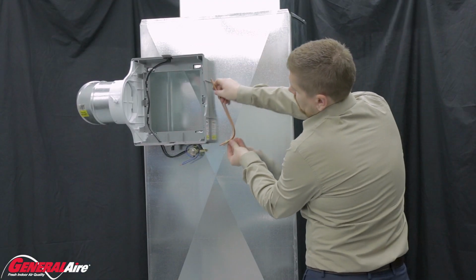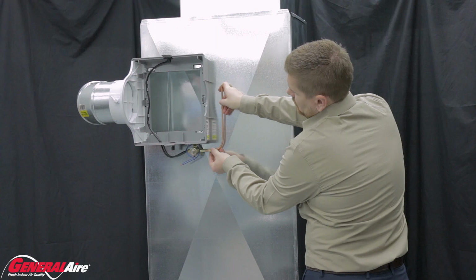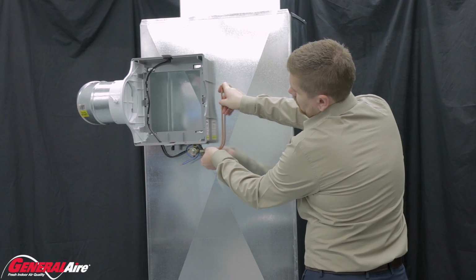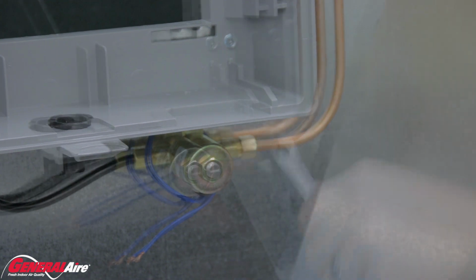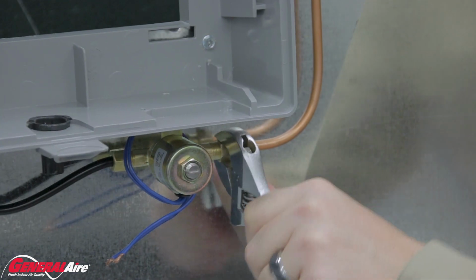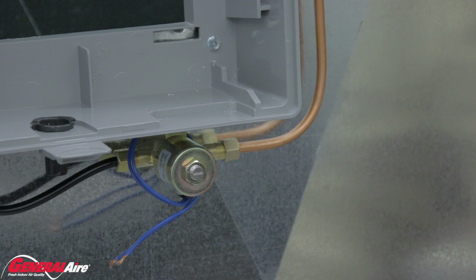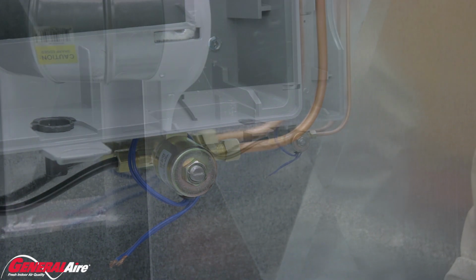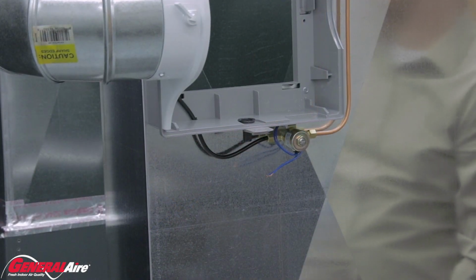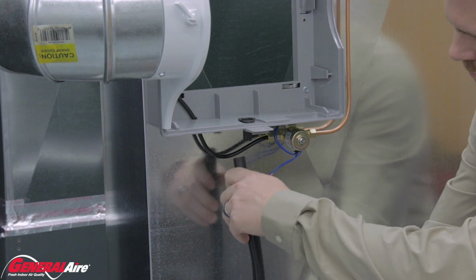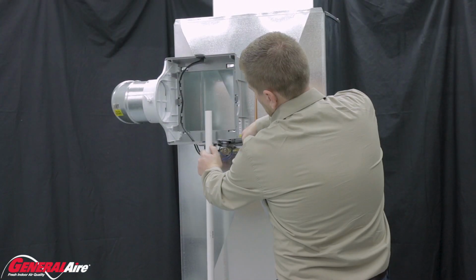Your water line runs down the side of the humidifier to the inlet of the solenoid. Take off the compression fittings and install the pipe, tightening the fittings back on with the crescent wrench using the same method as the saddle valve. The water supply is now set up. If using 5/8 tubing, connect the tubing to the drain nipple under the unit and run the line to the designated floor drain. If using 3/4 PVC rigid pipe, cut the pipe as needed utilizing the PVC fittings to run the drain line down to the floor.